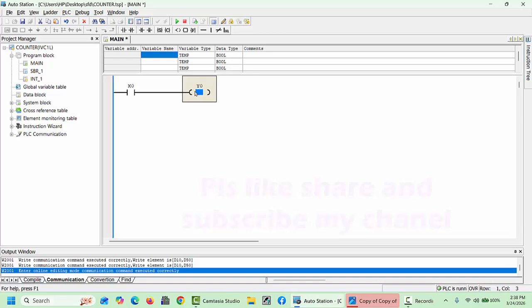We have to make three contactors, which look like y0, y1, y2. First we will make the simulation, and after that we will start. When we press this x0, our main contactor needs to start. For example, y0 is our main contactor, and the second contactor needs to start in parallel connection with this y0 for the star, and the third contactor will be for the delta.